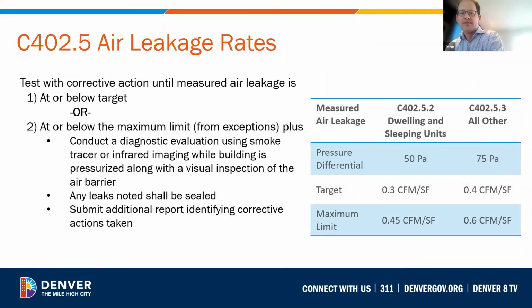So if the tested level is above the maximum limit of 0.45 for dwelling units or 0.6 for all other, then retesting is required. If it's between the target and the maximum limit, you can provide remedial measures and identification of air leakage without retesting.